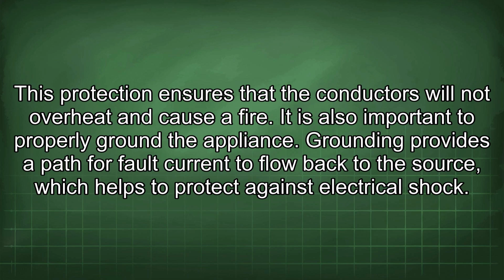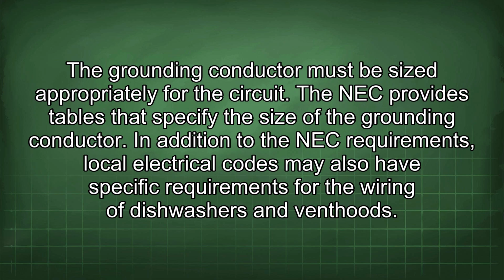It is also important to properly ground the appliance. Grounding provides a path for fault current to flow back to the source, which helps to protect against electrical shock. The grounding conductor must be sized appropriately for the circuit. The NEC provides tables that specify the size of the grounding conductor.